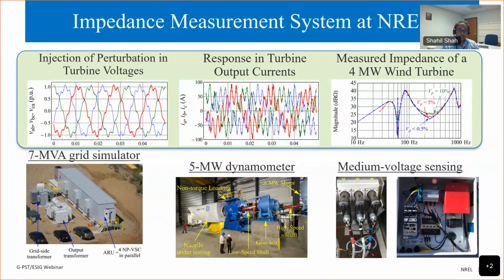So I think I have another 10 minutes, and in that I would like to cover the impedance measurement system that we have developed at NREL. This is like a hardware twin of the impedance scan software tool that I just described. We use our 7 megawatt grid simulator to measure impedances of different inverters and wind turbines. Right now, because of the limitation of grid simulator size, we can measure impedance of devices rated up to 7 megawatts, but we recently procured a 20 megawatt grid simulator, which is already here at NREL and which will be commissioned probably early next year. So we'll be able to scan impedance responses of even high power devices.